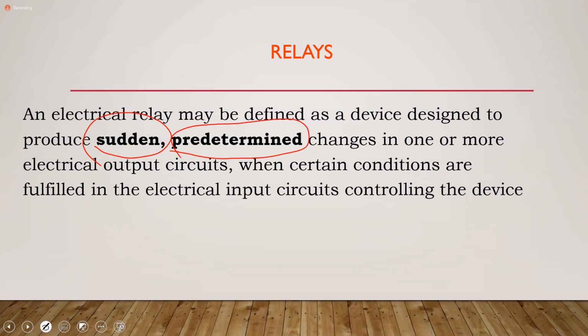A classic example is there are times when you have to transition load. So you're doing switching, right? And if you recall, when we were looking at the bus bar arrangements, one of the things we looked at was whether or not they were maintenance friendly. So sometimes if you're going to maintain a certain type of bus bar arrangement, you have to take off all the circuits. If you just want to look at one circuit, you have to switch off everybody. Now, the switching exercise that can take place may mean that you have to move a particular group of customers to a particular circuit, do what you have to do quickly, and then switch them back. So in switching operations, you may have to do that.